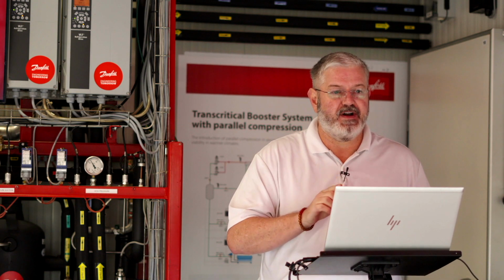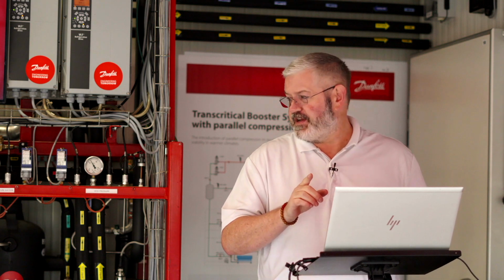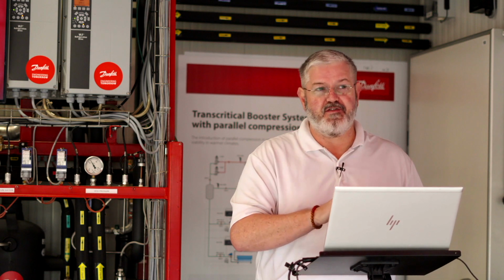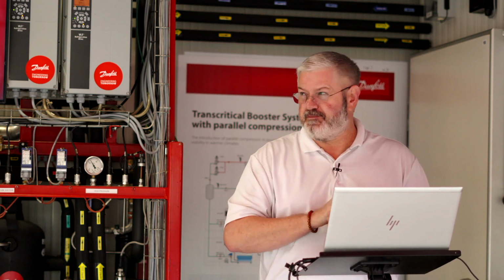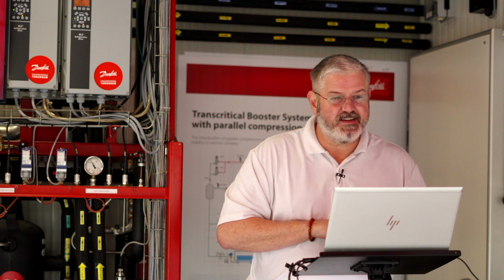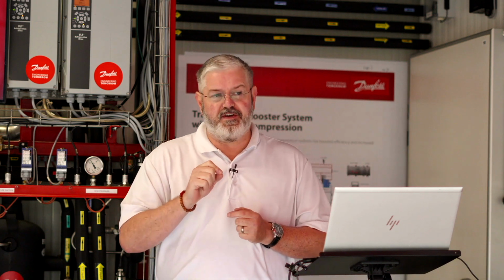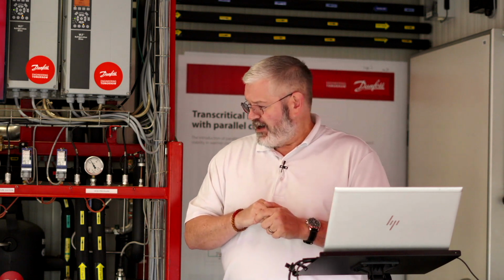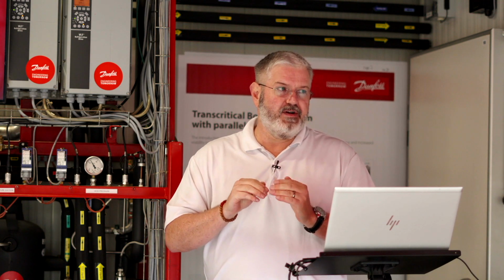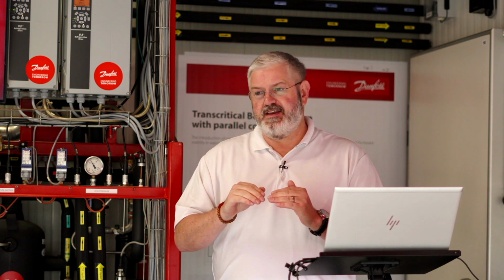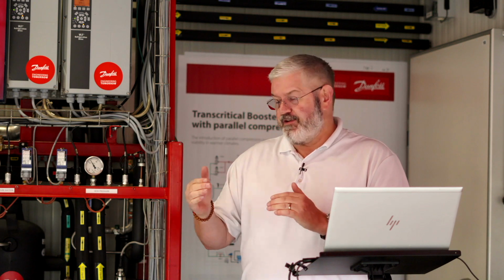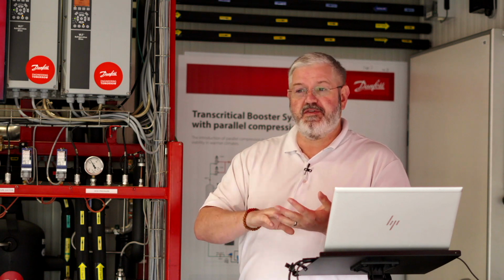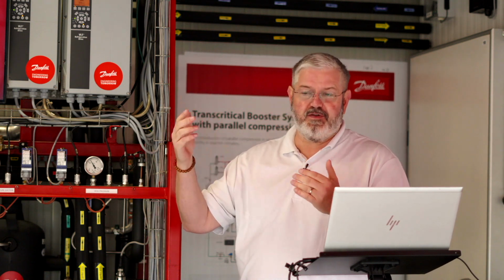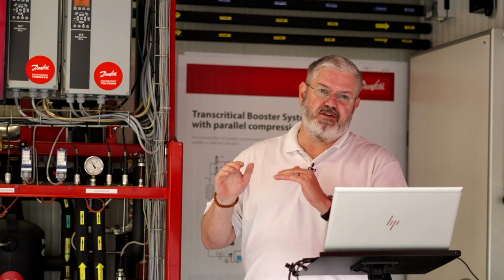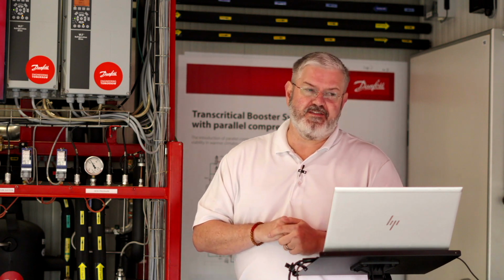All right, so the ejector. The questions on parallel compression and ejectors I'm going to hold off on answering for the moment, because we're going to cover that. I think the material is going to answer the questions. Let's see. I do have a question about whether dry ice can form during operation from inaccurate transducer readings. During operation, the answer would be no, because you're going to be about 200 pounds on your low temp side, not much below that. 200 pounds, I believe, is minus 22 or minus 20. And then you only go up from there. So flash tank is at 520, medium temp is at 400, and of course the discharge side, 800 to 1400. So you're never going to really see conditions below the 70 pounds that would cause you to form dry ice.